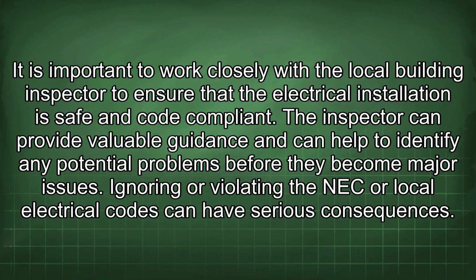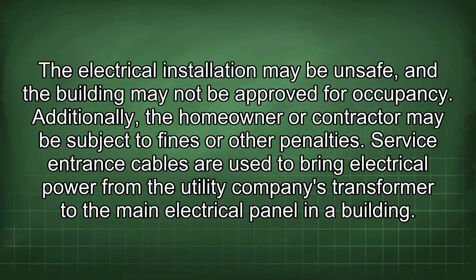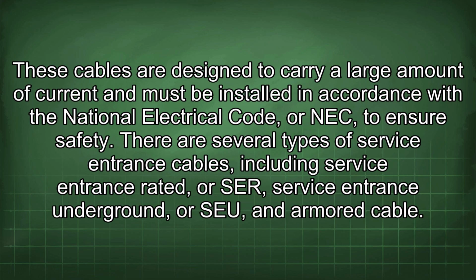Ignoring or violating the NEC or local electrical codes can have serious consequences. The electrical installation may be unsafe and the building may not be approved for occupancy. Additionally, the homeowner or contractor may be subject to fines or other penalties. Service entrance cables are used to bring electrical power from the utility company's transformer to the main electrical panel in a building. These cables are designed to carry a large amount of current and must be installed in accordance with the National Electrical Code, or NEC, to ensure safety.